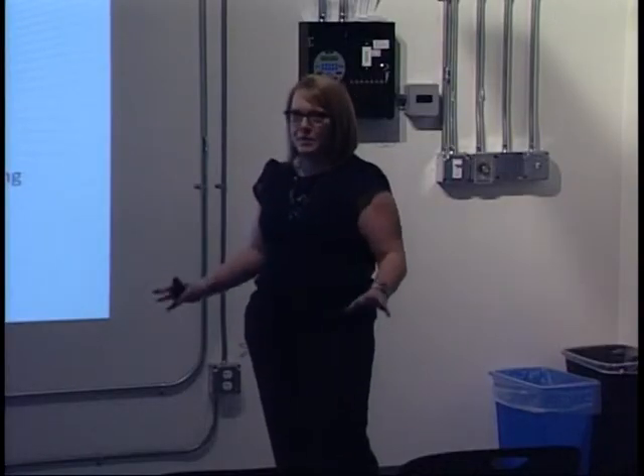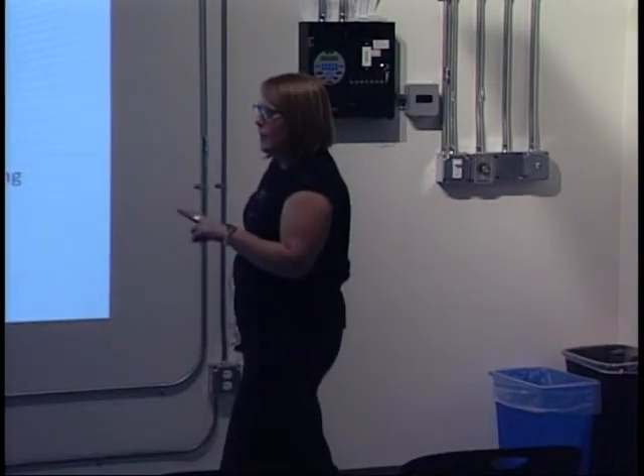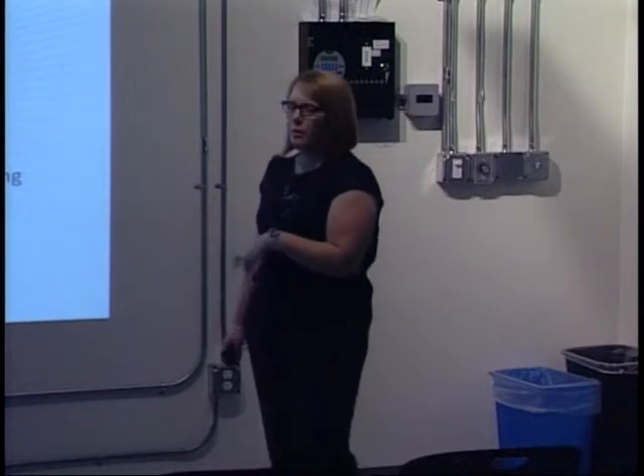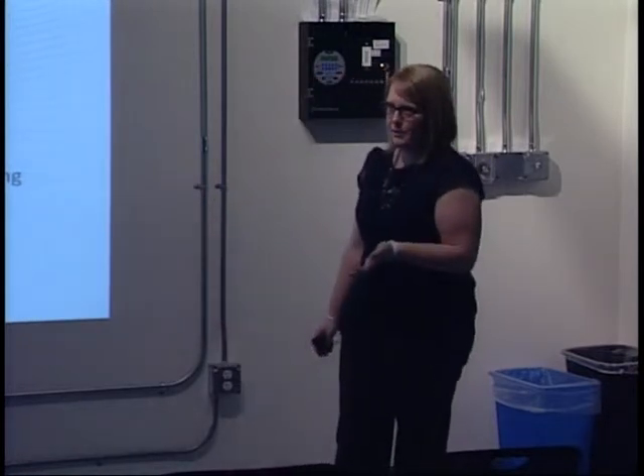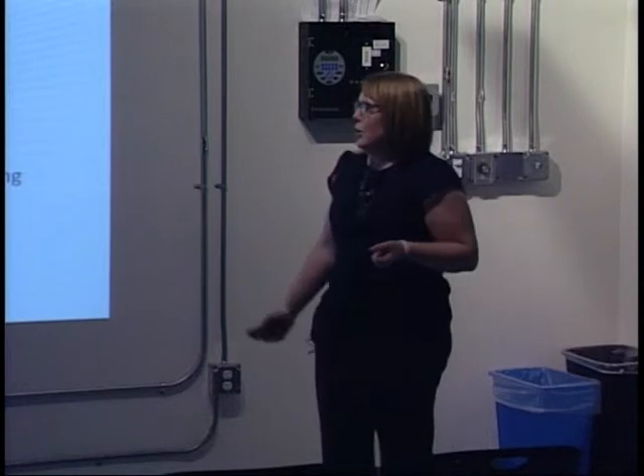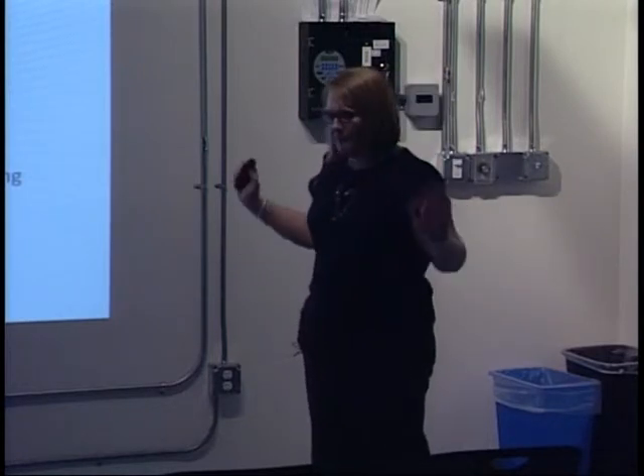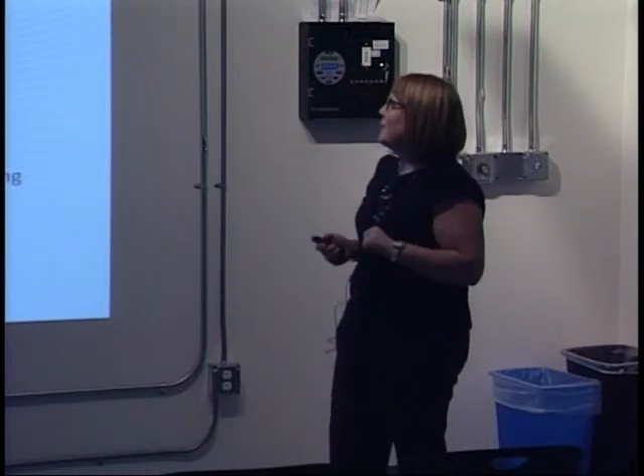They developed this work in order to implement displacement ventilation in several hospitals in California. Since this report came out, the NIH has put their stamp of approval on this method - it's NIH approved. There are at least two hospitals in California under construction now that are displacement ventilation hospitals, so it's a burgeoning way to do this, and it's showing to be effective.